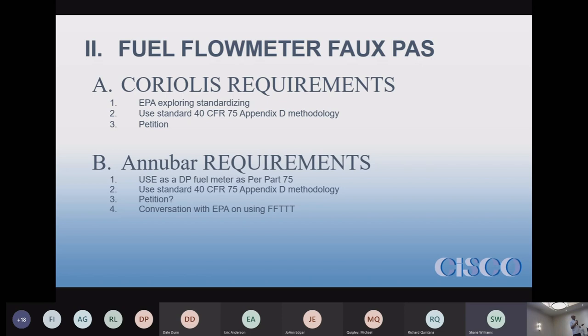You have an option with those types of meters that you don't have with a standard meter. It allows you to do a transmitter transducer test, so you can calibrate the transmitter instead of calibrating the flow meter itself, which makes it nice. You don't have to take the meter out, just calibrate the transmitter. Because this particular site saw the similarity, they were using the transmitter transducer test to meet Part 75, but that's not permitted, even though their similarities are almost identical. And so that's why there's a question mark by the petition.